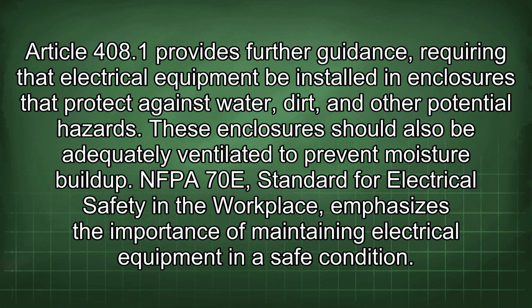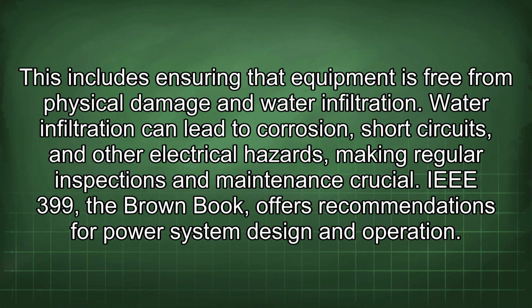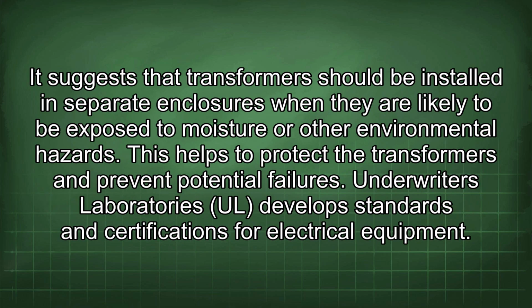NFPA 70E, the standard for electrical safety in the workplace, emphasizes the importance of maintaining electrical equipment in a safe condition. This includes ensuring that equipment is free from physical damage and water infiltration. Water infiltration can lead to corrosion, short circuits, and other electrical hazards, making regular inspections and maintenance crucial. IEEE 399, the Brown Book, offers recommendations for power system design and operation. It suggests that transformers should be installed in separate enclosures when they are likely to be exposed to moisture or other environmental hazards. This helps to protect the transformers and prevent potential failures.